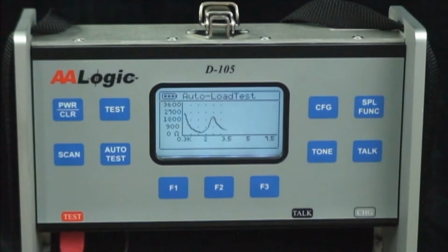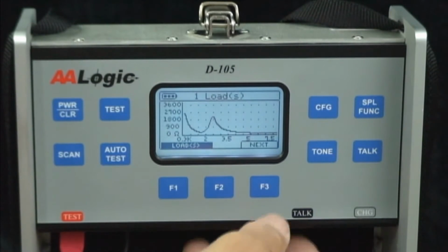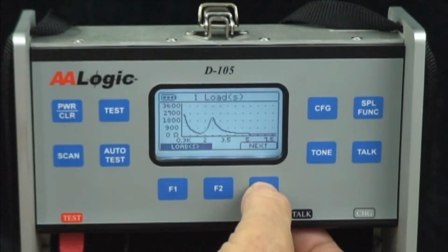The test will go into the automatic load test. It shows one load in this particular cable pair. The automatic load test will be run whenever a vacant pair is detected, a pair that does not have voltage. The next button will continue the auto test process.